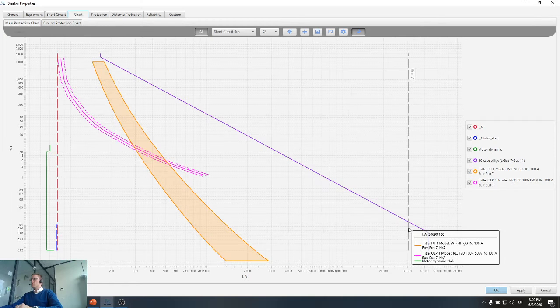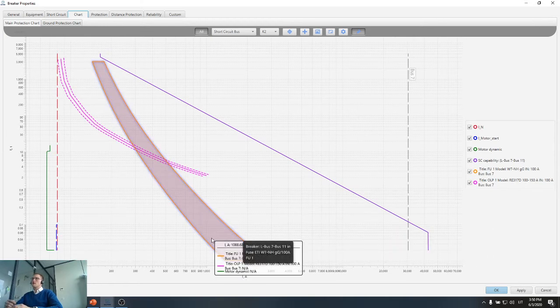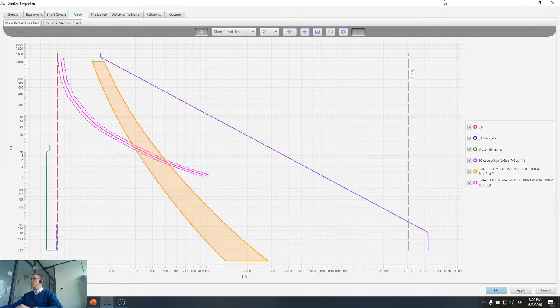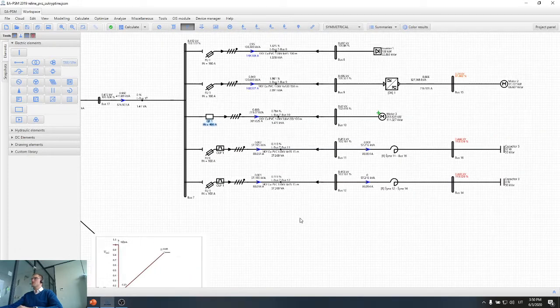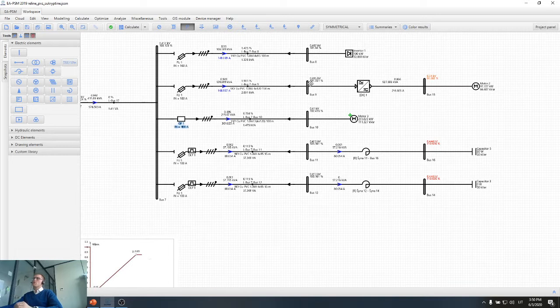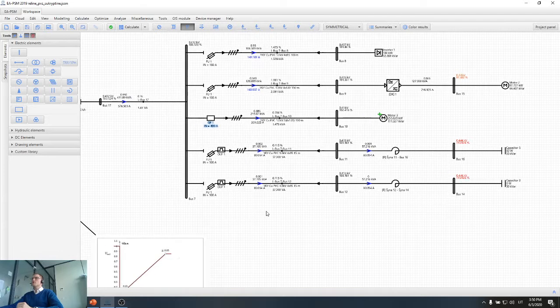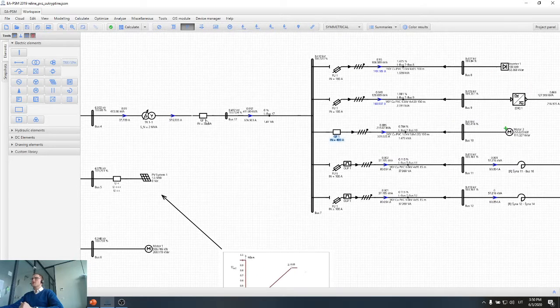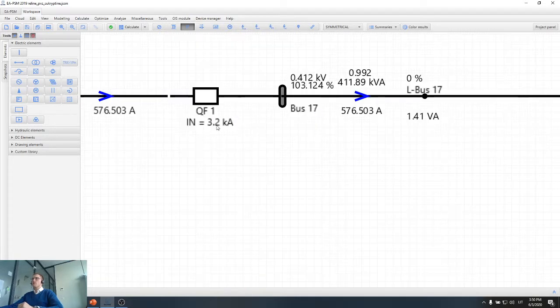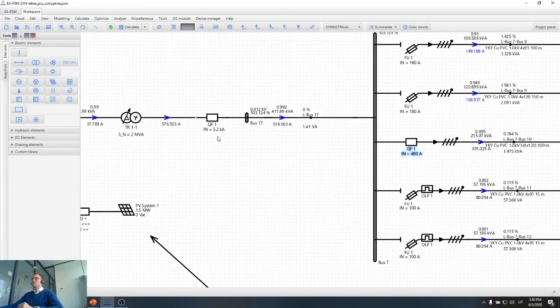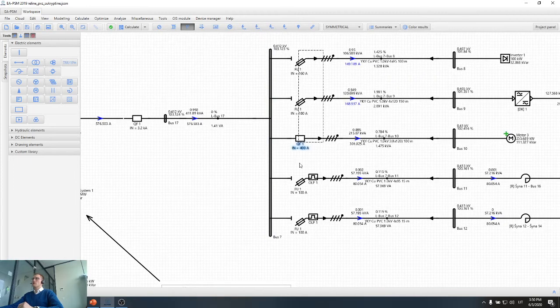So in case of short circuit, the fuse will blow very suddenly in a short amount of time and will protect the capacitor itself. So here we have discussed main protection devices for main equipment in the low voltage side. And of course each protection, as I have mentioned, should have a backup protection. So the backup protection in our case is this incomer breaker here. It's quite a big breaker, 3.2 kiloamps nominal current. So this breaker should work selectively with all the protections which we have shown here, which we have analyzed here.